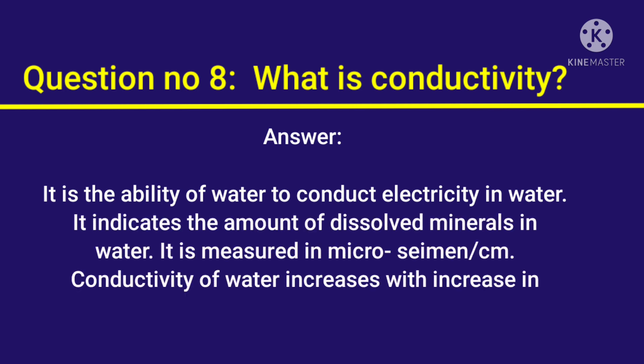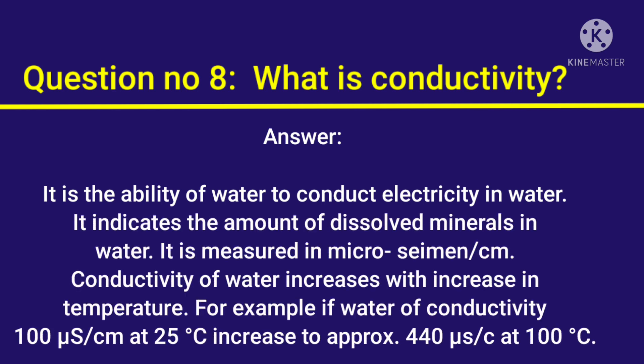Question number 8: What is conductivity? Answer: It is the ability of water to conduct electricity. It indicates the amount of dissolved minerals in water. It is measured in microsiemens per centimetre. Conductivity of water increases with increase in temperature — for example, water of conductivity 100 microsiemens per centimetre at 25°C increases to approximately 440 microsiemens per centimetre at 100°C.